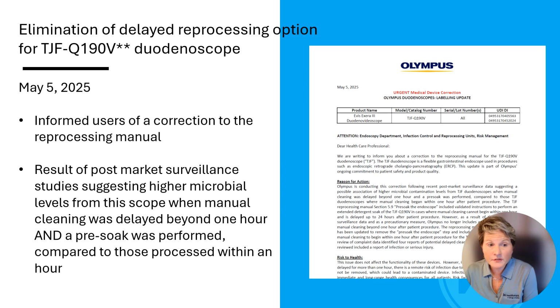But it's the result also of a post-market surveillance study suggesting higher microbial levels from this scope when manual cleaning was delayed beyond 1 hour and the pre-soak performed. So even when you're following what they had said was the manufacturer instruction for use, if you had to delay past an hour and you were doing the soak as instructed, they still found that compared to those scopes that were processed within the hour, these were in worse shape. They had more microbial burden on them.